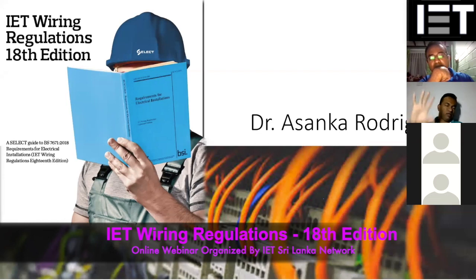But when you look at the earth connection from the equipotential bonding bar to your earth electrode, compared to the earth electrode resistance, this cable resistance is negligible. In most cases, the major component comes from the earth electrode, and because of that, the earth connection resistance is immaterial. But it's always better to reduce the cable length, meaning reduce the impedance, or if it is too long, you can use a bigger cable to minimize the resistance in that cable. That is the requirement. Otherwise, if you can maintain the touch potential at a maximum of 50 volts, then that is fine.